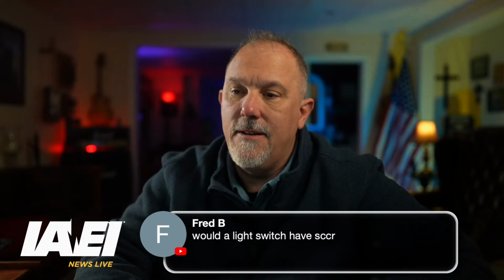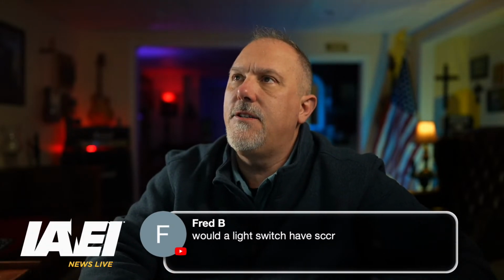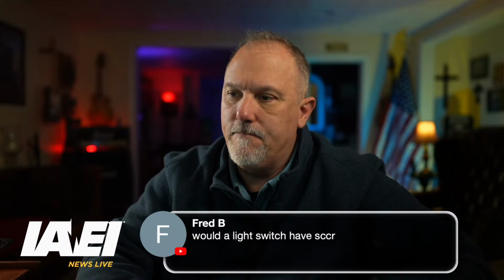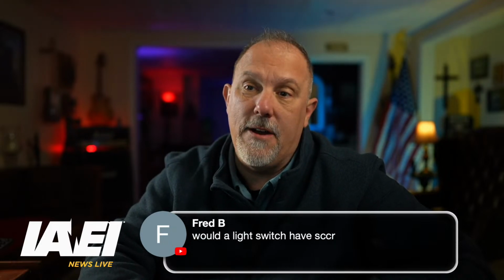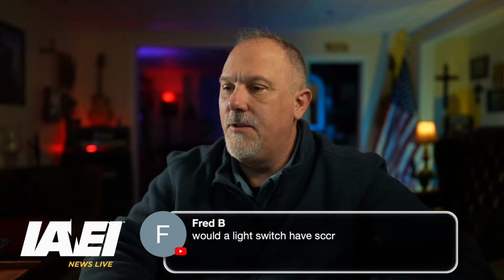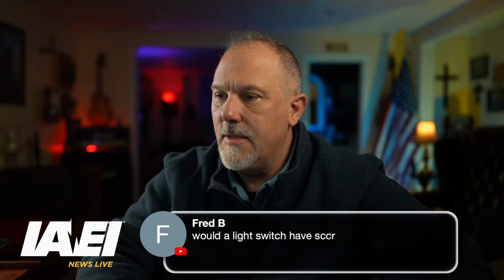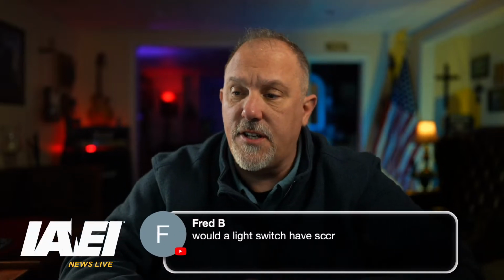So we could always take a look at the standard, and maybe, Fred, I can do that after a while. And maybe that'll be a good Q&A Friday for IAEI News Live. But if it's carrying fault current, just think about it. That light switch could be at the source of any in the power distribution system. Every component in a power distribution system is going to carry fault current, so it has to do it safely, right?